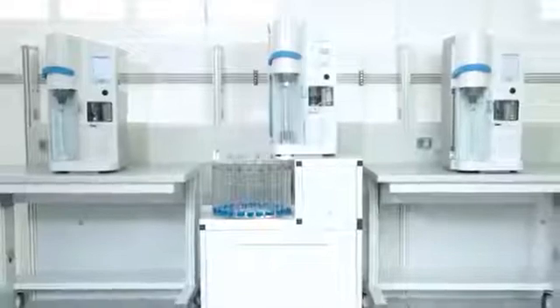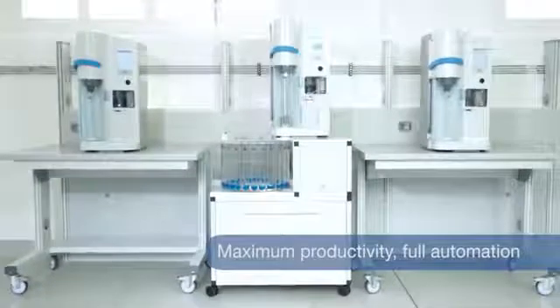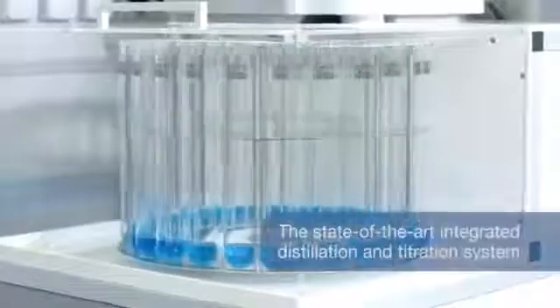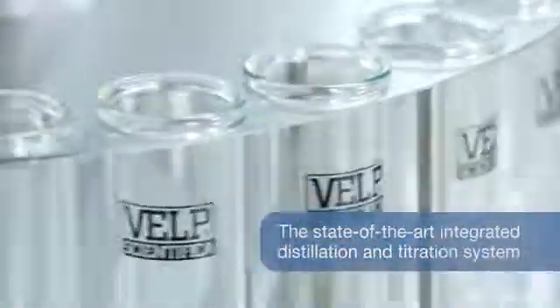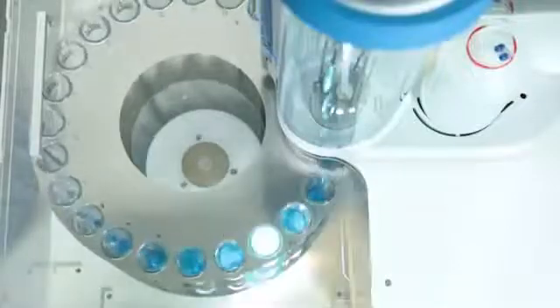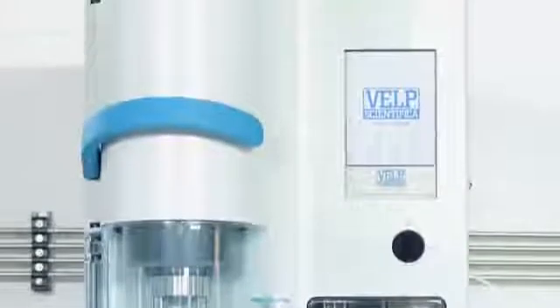The VELP UDK169 with AutoKjel AutoSampler ensures continuous operation and provides a simple and high-performance solution for safe and automatic distillation and titration. It achieves the most reliable results with colorimetric titration based on precise chemical reactions in Kjeldahl analysis.